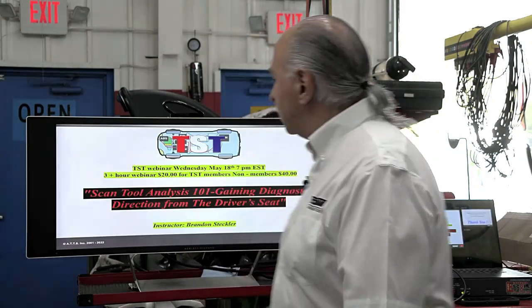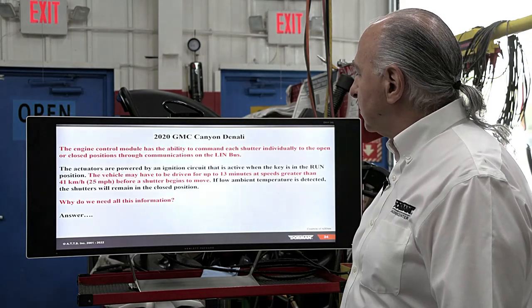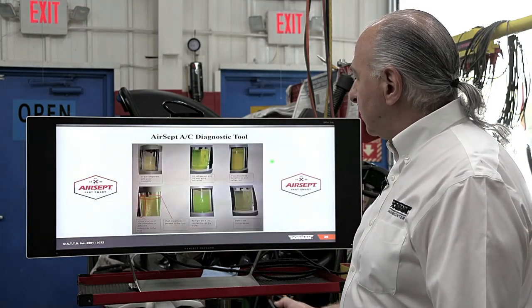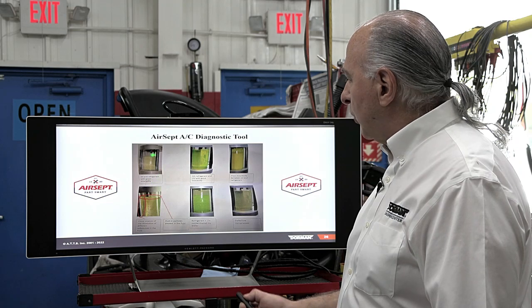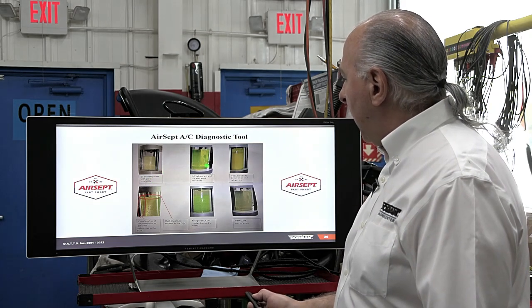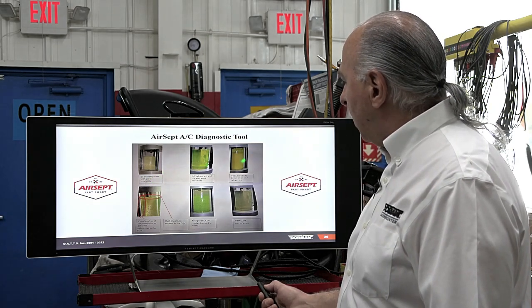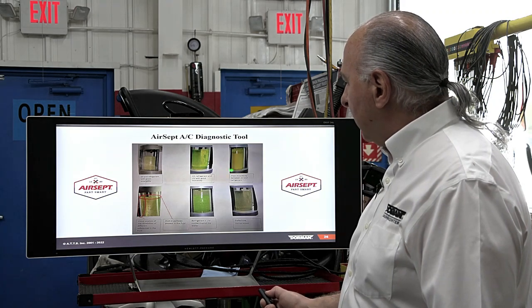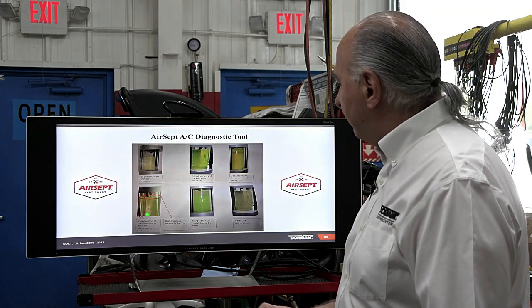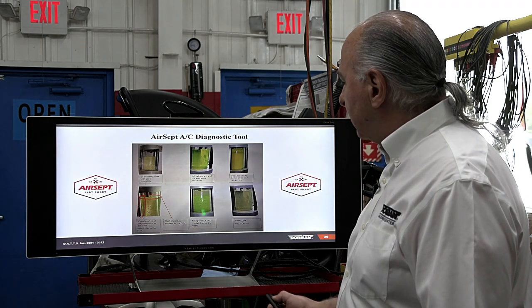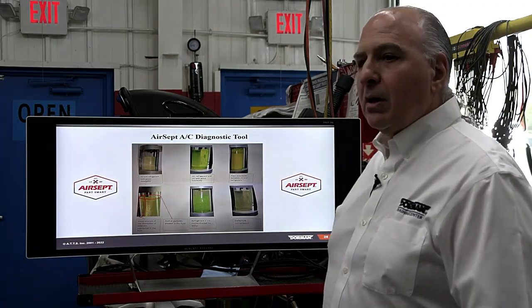The tool with the glass, I think I explained it, shows you the amount of oil if there's a problem. You could go back to your slides right here if you want to diagnose it, right here from AirSept. This will give you, if you have oil and refrigerant with good miscibility, and right here with dye in it, poor is like a separation, okay? You could have debris inside of it with particles. You could have contamination with water. How do you get water? Moisture in the system, right? Moisture. And moisture and 134A and 1234YF create hydrofluoric acid.